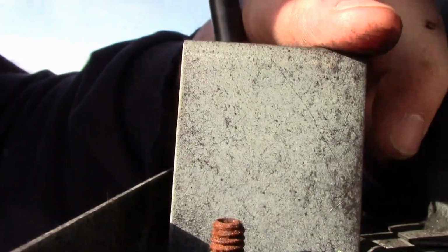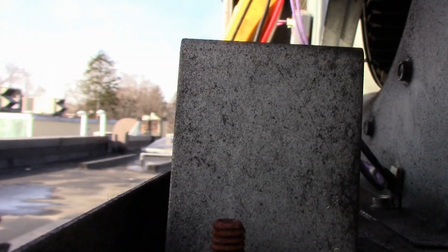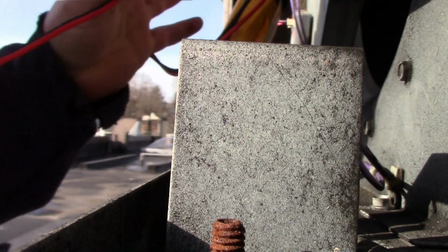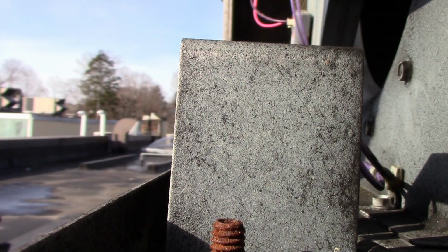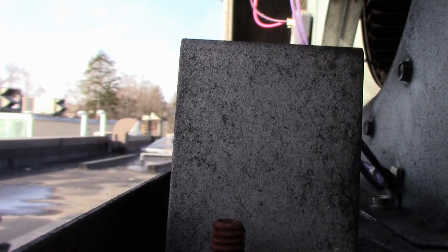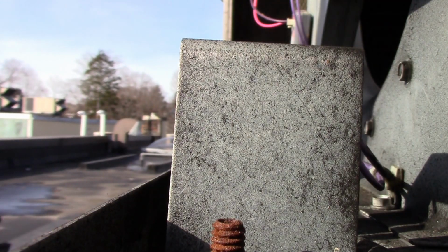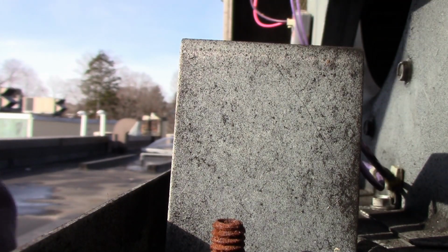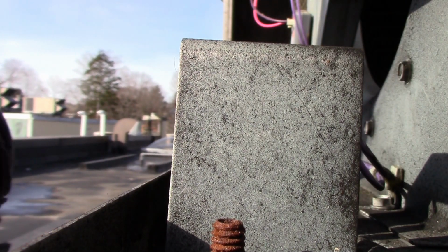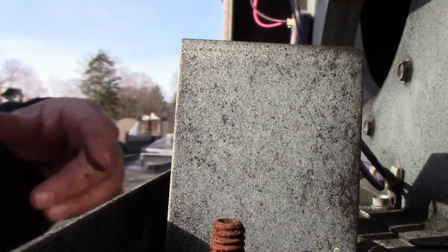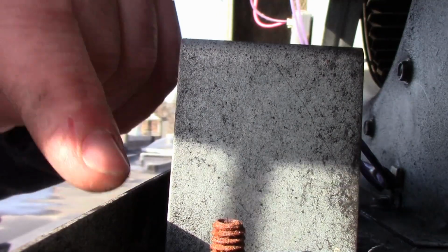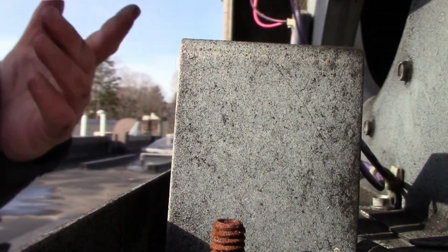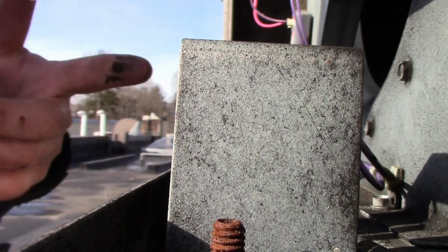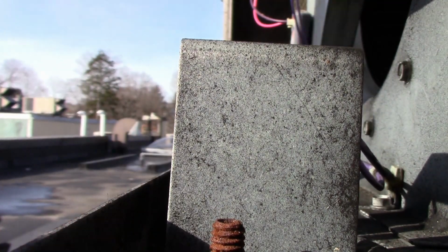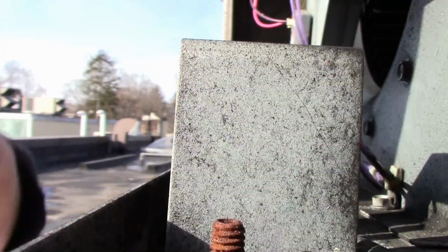See, the biggest problem is you'll get a lot of people that will read those codes and it'll tell you what's wrong with the unit, what switch is off, and they'll go right to that part and replace that part and not figure out the cause of it. So if you were to just replace this part, yeah, it'll probably run while you're here for the 10 minutes watching it, but as that heats up, that's going to trip, because we're not getting any airflow. So you have to go to the heart of the matter, basically.